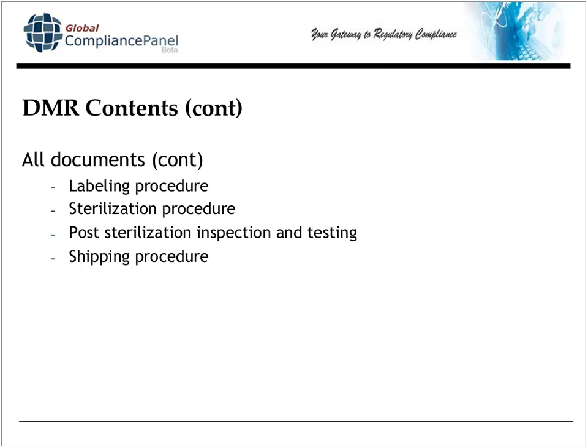Post-sterilization inspection and testing needs to be in your DMR, as does your shipping procedure. Some firms don't have shipping procedures; others do. There's no explicit requirement for shipping procedures, but if you have it as part of your quality system, it must be included in your DMR.